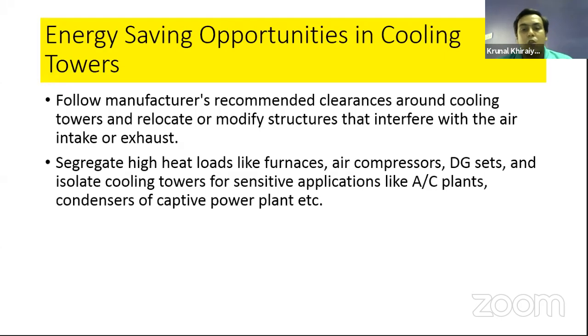Segregate, yes, this is very important, and this is the last point of today's energy saving opportunity. Suppose I have designed the cooling tower to accommodate a heat load of only our process utility. But after that, suppose I installed the DG set, different furnaces, a different air compressor, and I have merged all the cooling systems in the same cooling tower.